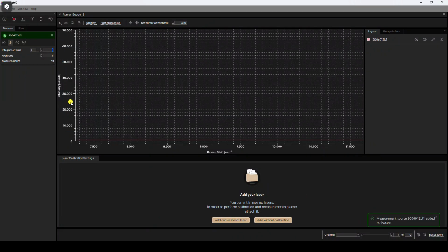To perform a dark reference, you need to turn off the laser if it is already turned on. Start a measurement, press the Start button. Click the Save Dark Reference button to capture the dark baseline spectrum. Choose the Scope minus Dark option in the Scope menu to check if your dark reference has been saved correctly.